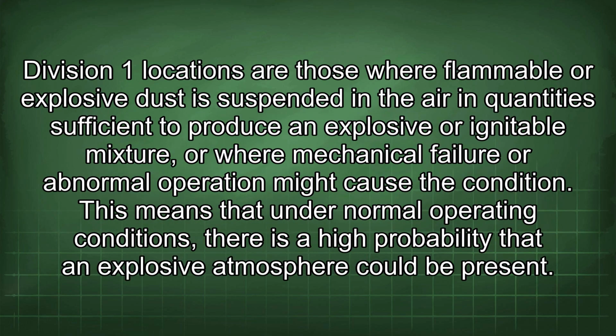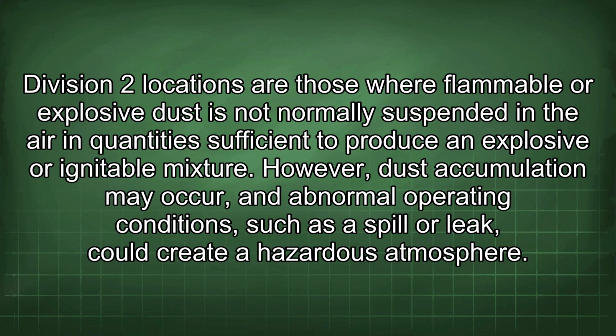Division 1 locations are those where flammable or explosive dust is suspended in the air in quantities sufficient to produce an explosive or ignitable mixture, or where mechanical failure or abnormal operation might cause the condition. This means that under normal operating conditions, there is a high probability that an explosive atmosphere could be present. Division 2 locations are those where flammable or explosive dust is not normally suspended in the air in quantities sufficient to produce an explosive or ignitable mixture. However, dust accumulation may occur, and abnormal operating conditions, such as a spill or leak, could create a hazardous atmosphere.